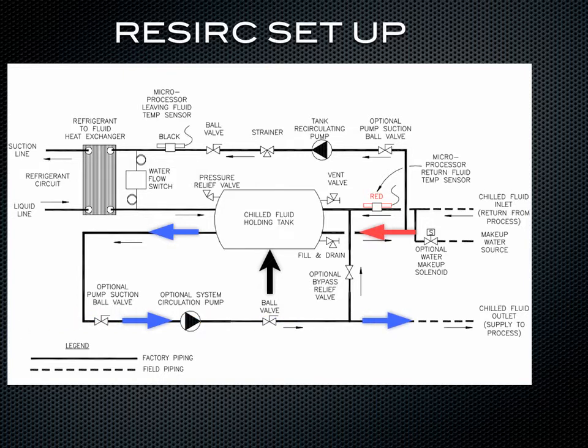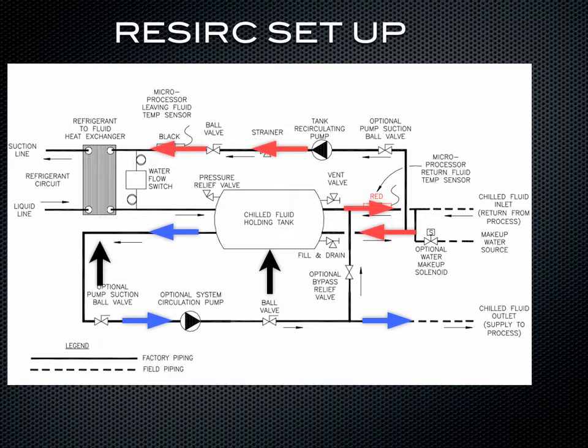The second loop is the recirculation loop. Anytime the tank gets above 55°F — say 56° or 57° — the refrigeration system will turn on. It will pull that water through the recirc pump to the chiller evaporator, where the heat is removed over to the refrigerant side. Then you have your desired leaving water temperature returned back to the tank to mix with that fluid.